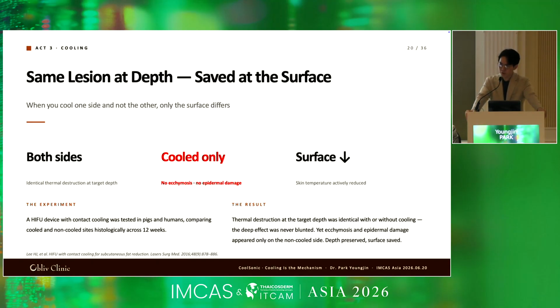So when you compare the HIFU that was actively cooled with the HIFU that was not cooled, you can see that only with the cooled HIFU, there was no ecchymosis and no epidermal damage, meaning that there will be less downtime for the patient, especially because when you use a very high power, high fluence with the HIFU, patients sometimes become very puffy, and there's a lot of redness after the treatment. And some patients actually have the redness for a certain amount of time and complain about that, but that normally happens because of the accumulation of heat. And accumulated heat actually generates damage in other parts of the tissue that you haven't treated.